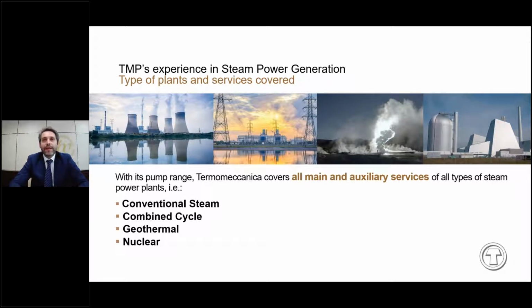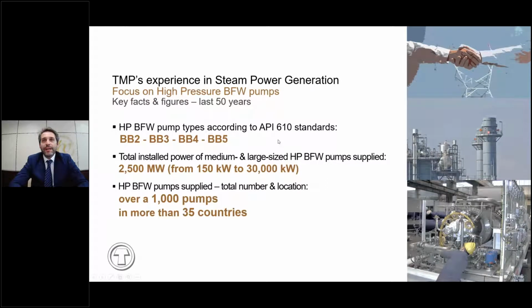In our history, we have supplied pumps for different types and technologies of power generation plants, from conventional steam to combined cycle, geothermal and nuclear. Mainly we supply the main pumps of these power plants, which are boiler feed pumps, condensate extraction pumps, water cooling pumps, and intakes. The boiler feed pumps can be realized according to different API 610 configurations: BB2, BB3, BB4, and BB5. We have experience in all of them, and in the next slides we will show some references for each type.